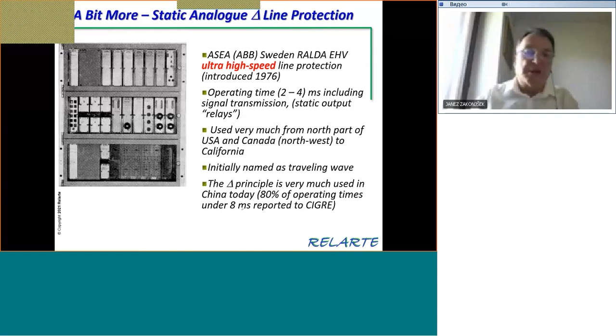Then we come to this RASFE relay, which, as you can see here, is also a static relay, but digital. Why digital? Because all the signals, current and voltage, how they were formed, everything was changed into digital form. That means only 0 and 1. And then inside the logic, it was decided whether there was a fault or, for example, whether impedances were inside the protected zone or outside of it. So only digital form of signals was used here.